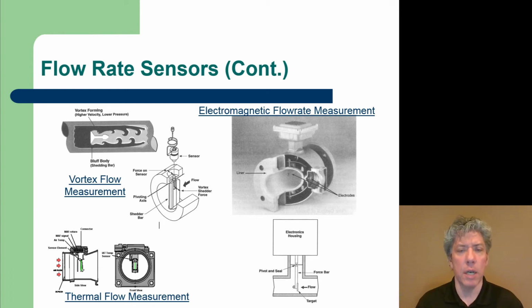Another way to measure flow rate is by heating up a resistance so that the temperature of it goes up, and then controlling the current going to that resistor so that you maintain the temperature constant. As air flows by, for example, it will cool the resistor, and so the temperature will tend to drop. So you have to pump more current into the resistance element in order to bring the temperature back up to the set point. By measuring the amount of current required to maintain the temperature of the resistance element, you can calculate or back calculate the air flow rate. Another common method is, rather than holding the temperature constant, to put constant current into the resistance element and measure the resulting temperature. Again, this can be calibrated to give you the air flow rate going past the sensor. And I don't remember which way cars typically work. It's one or the other.